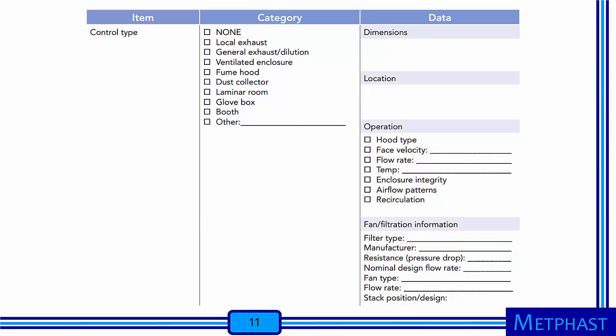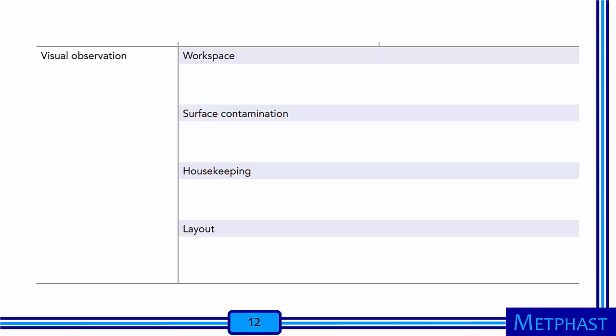A specific category is provided for controls, including a place to note the type of control, the dimensions, location, operating characteristics, and more specific information about the hood type, any airflow recirculation patterns, and velocities measured. Also, there is information about filter type, manufacturer, resistance of the control device, the fan type, the flow rate through the system, and any stack position or design characteristics. Lastly, space is provided on the walkthrough checklist for visual observation, surface contamination, housekeeping, and physical layout.